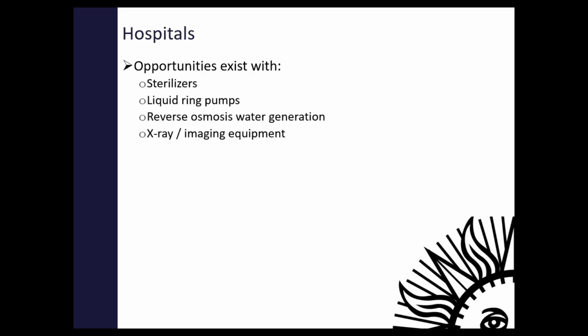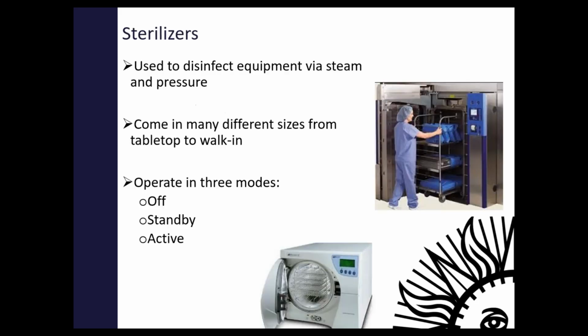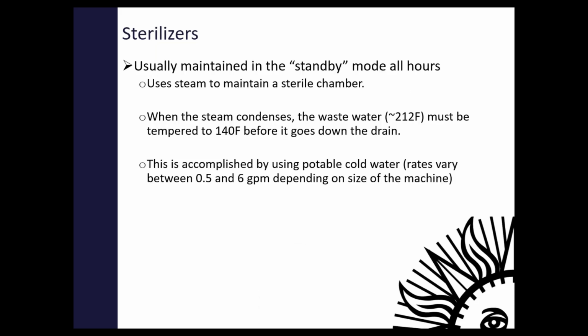Hospitals have some equipment that you can optimize: sterilizers, liquid ring pumps, which I don't really see too often, reverse osmosis, and x-ray machines. So sterilizers, really just make sure that they shut them off when they are done using them. They usually put them into a standby mode. If it's a clinic, and they're only open from 8 a.m. till 6 p.m., then they have no procedures after that. You should probably recommend they shut down their sterilizers after that, because then they're just maintaining a ready temperature, even though no one is going to put a load through the sterilizer.